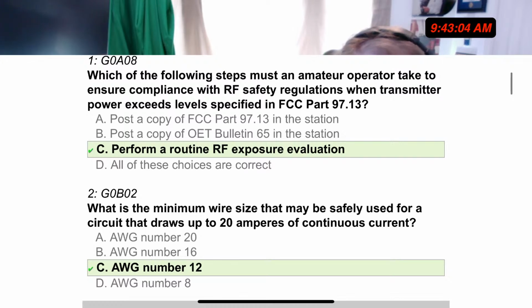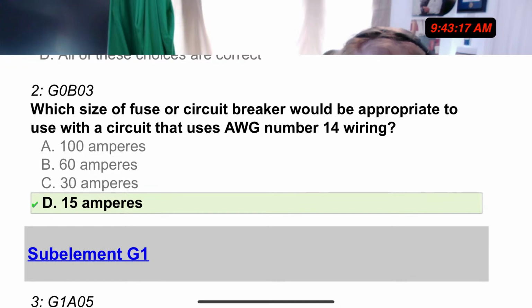Now you see the difference here. On a 20 amp circuit you need wire gauge 12, a thicker wire than what you have here on the 15 amp, which is your typical bedroom circuit, average wire gauge 14, okay? So it's not enough just to throw a 20 amp circuit breaker in your circuit breaker box and call it good. Or go the extra step, put yourself the 15 amp circuit breaker, and then throw a 20 amp circuit breaker and a 20 amp plug-in and say we're done, because you still have 14 wire gauge running through your walls. You're going to draw too much amperage and you could cause a house fire. That's why you don't want to do it.